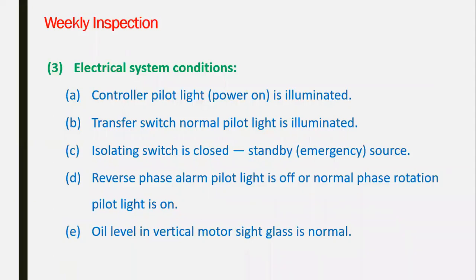Going to the driving system. For the electrical system, you see the controller pilot light for power on is illuminated, assuring that there is continuous power on. The transfer switch pilot light is illuminated. The transfer switch, which we call ATS, automatic transfer switch, transfers between the normal supply and the emergency generator. The light itself is on, illuminated in auto mode.